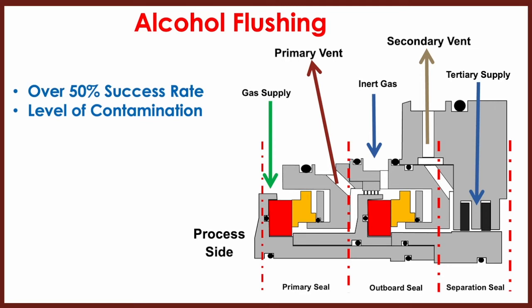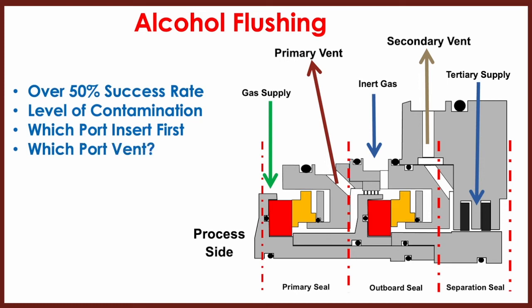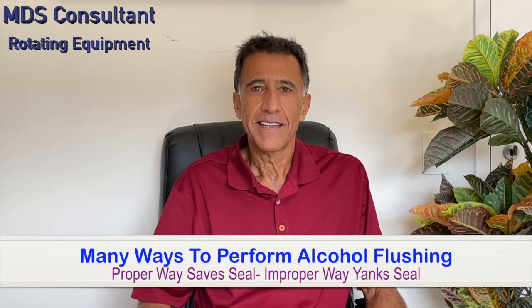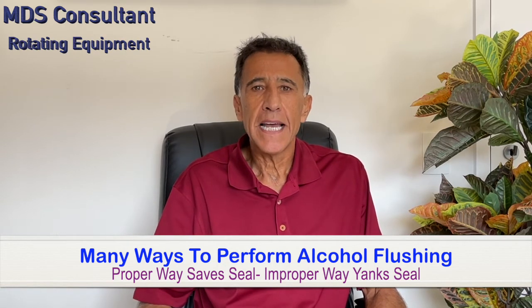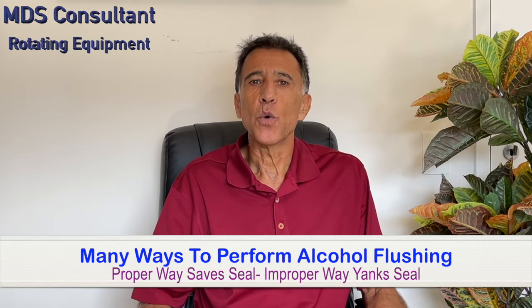Now, how exactly you would do the flushing would depend on your seal type and the number of ports you have. First, you have to figure out which seal most likely is stuck, which port to pump the alcohol into the seal first, and which port or ports to keep open as vent. As you can see, there are 3 or 4 ports to push alcohol into a given cavity. And by closing 1 or 2 others would kind of force the alcohol to go in a certain direction. So yes, there are many ways to skin this cat. There's a right way that would save your seal, and there is an ineffective way that you will have to yank out the seal.